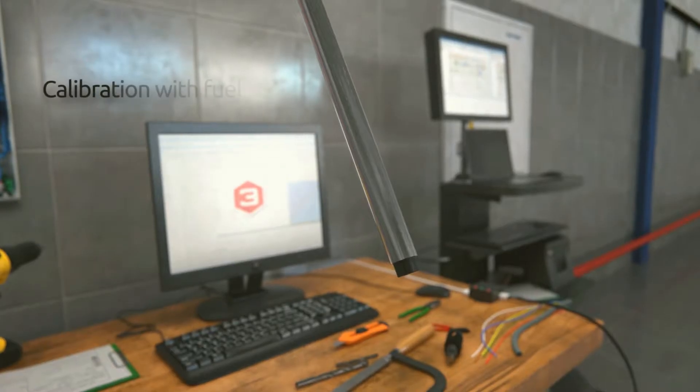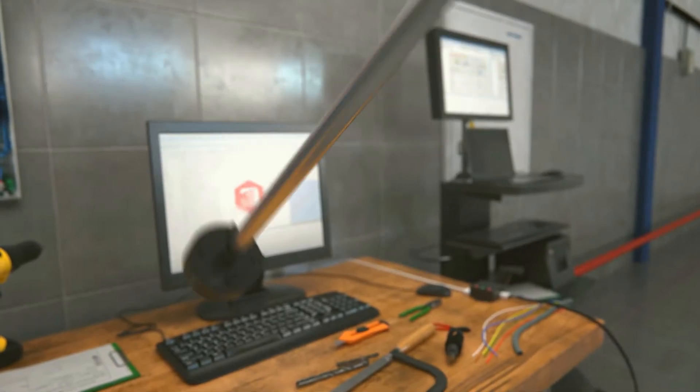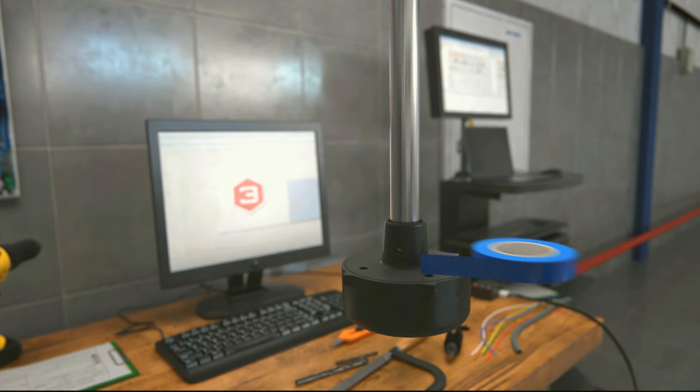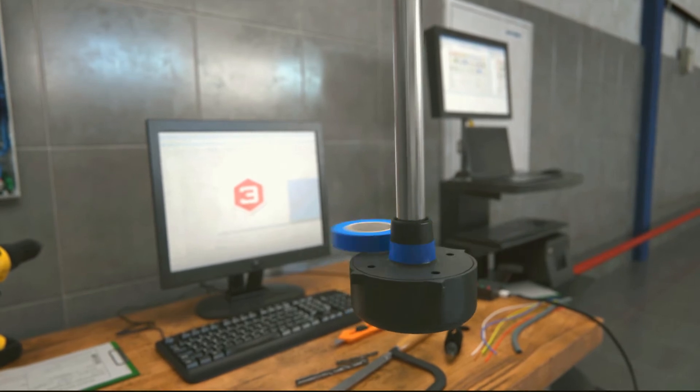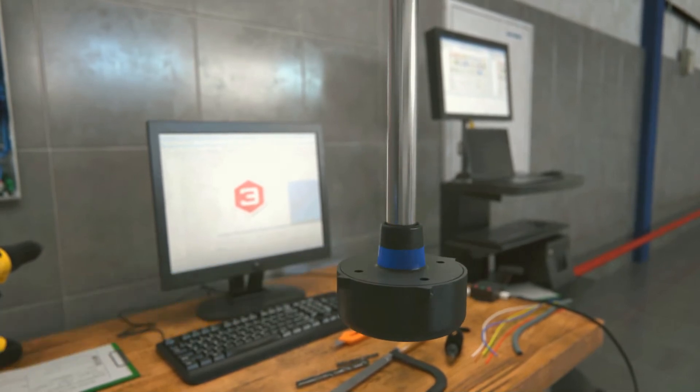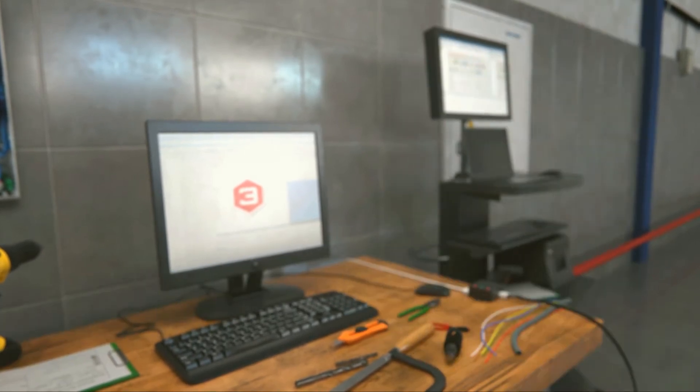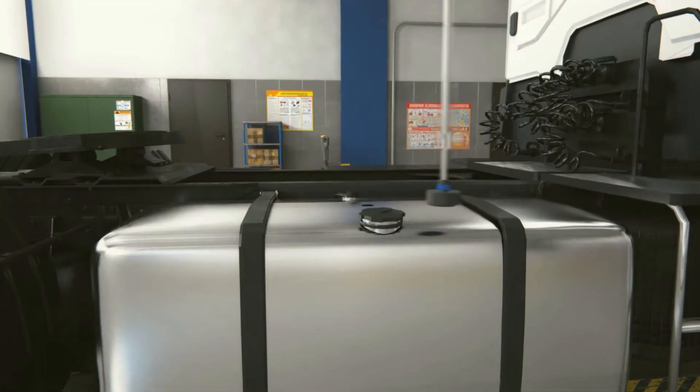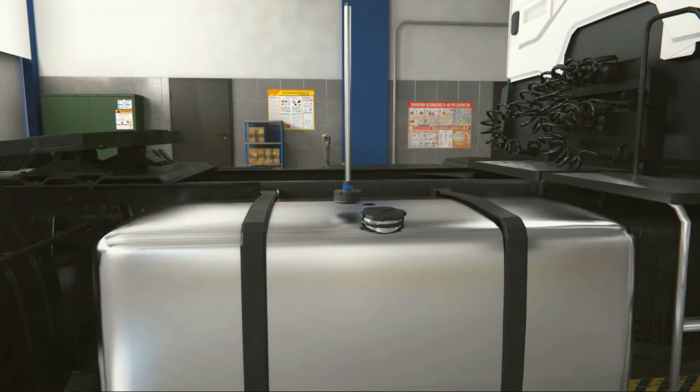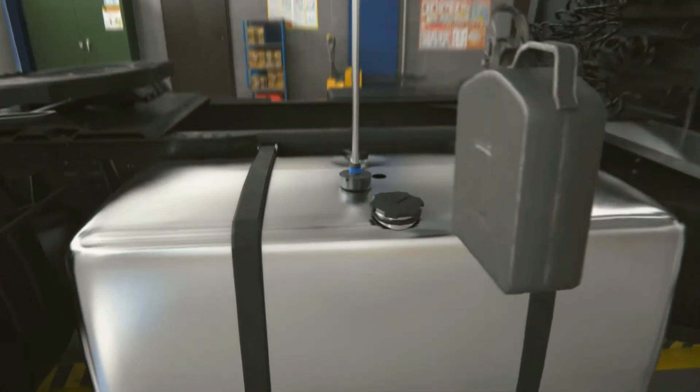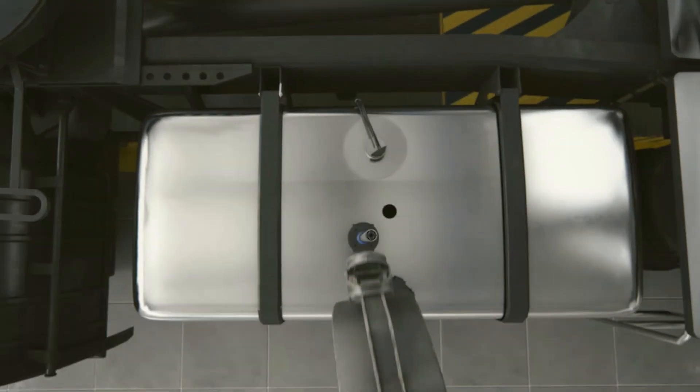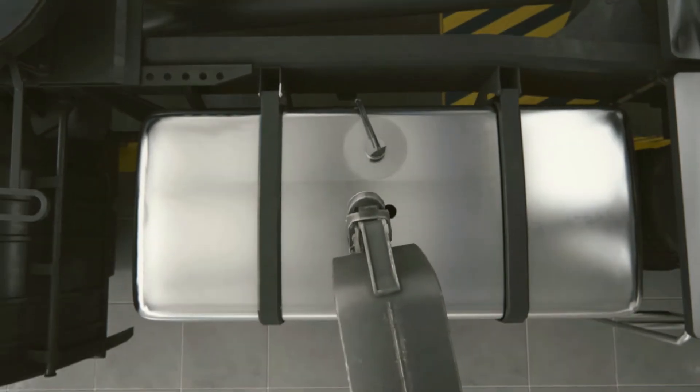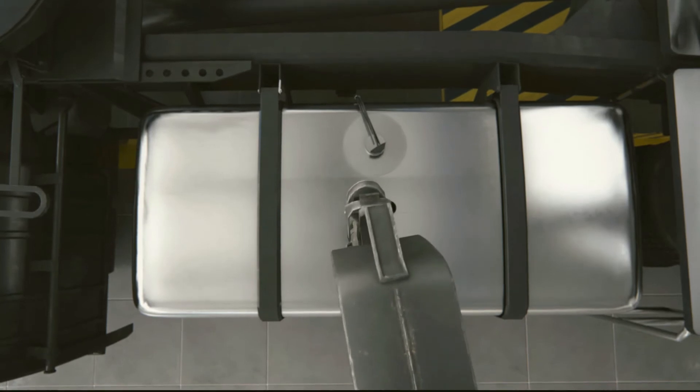Calibration with fuel. Cover the drain edge holes of the tubes with a piece of insulation tape. Turn the sensor upside down and put it on a steady surface. Fill the tubes with fuel using a jerry can with a narrow outlet.